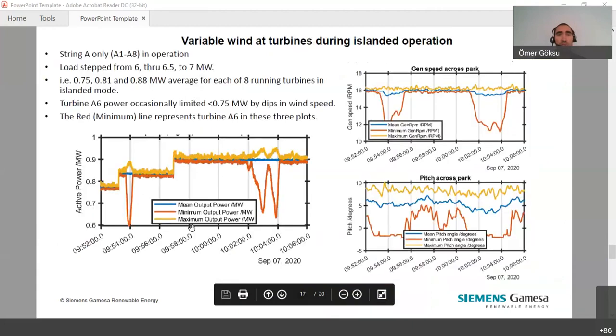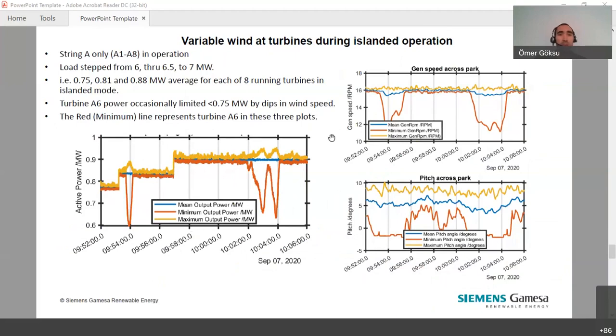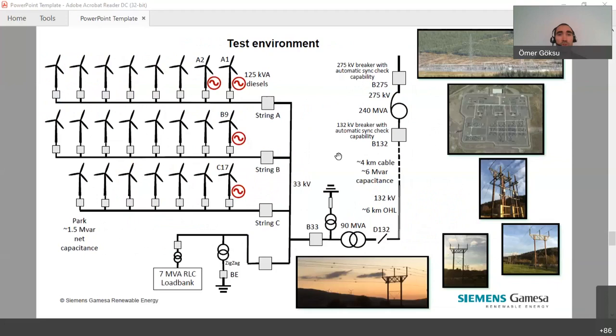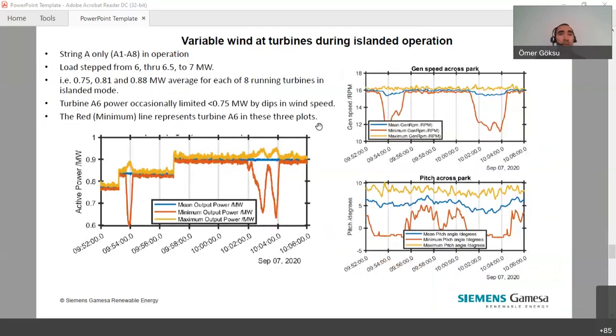And here we see the results from islanded operation, and the wind was, as I said, quite varying. And in this slide, we see only the first string. Let me go back quickly. Yeah, the first string A was the only string with turbines active, the rest disconnected, and they were feeding the local load. And the local load was stepped from 6 to 7 megawatts, responding to 0.75, 0.81 and 0.88 megawatts on average for these 8 turbines.